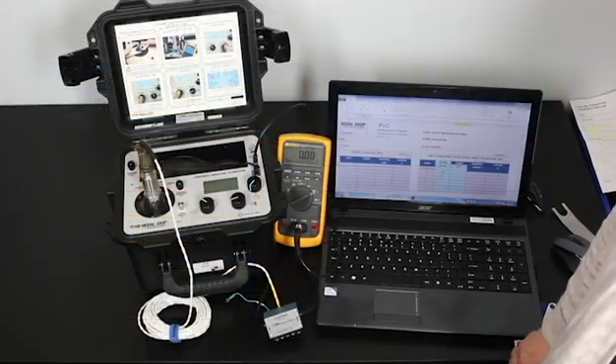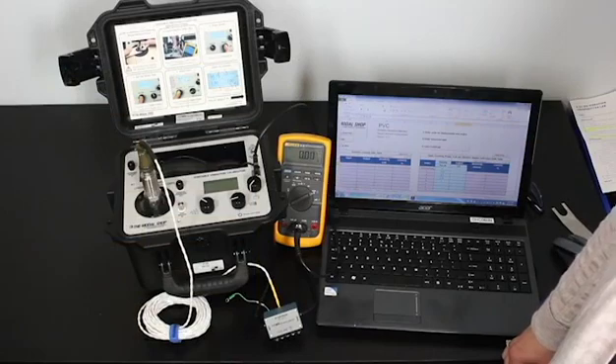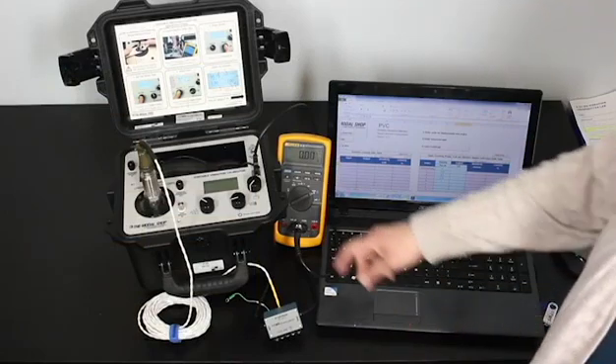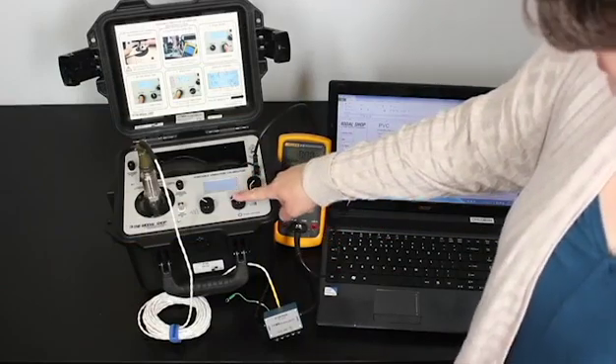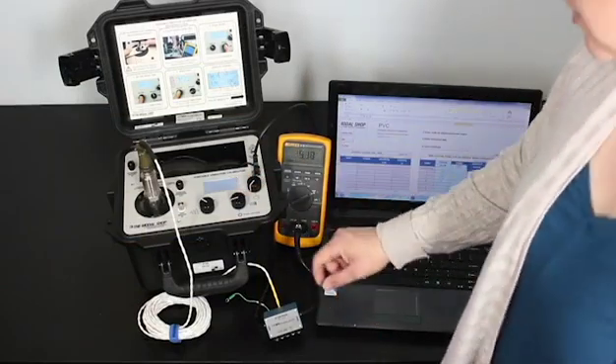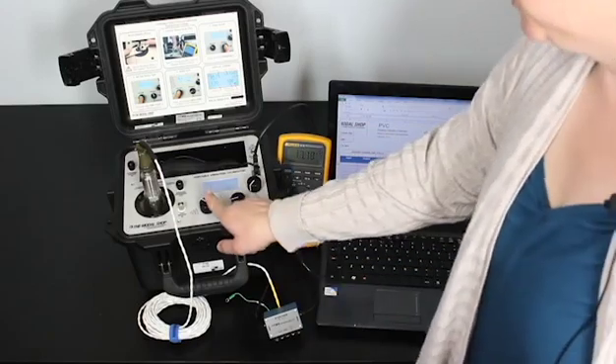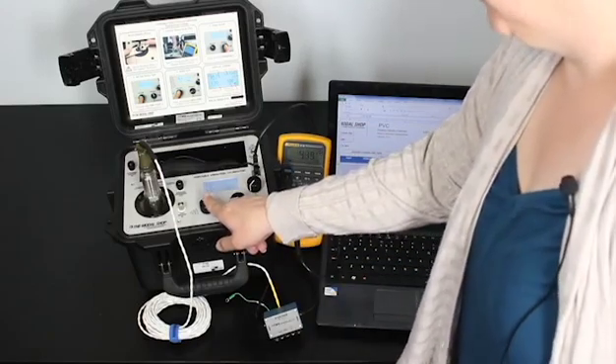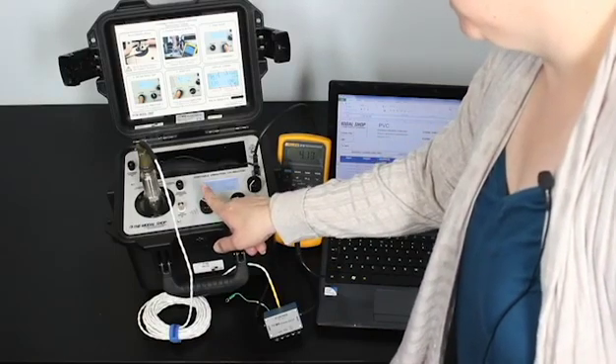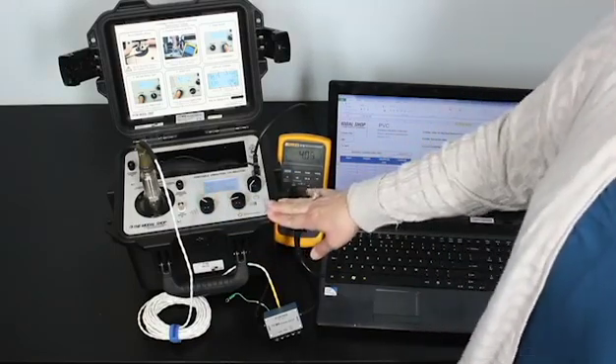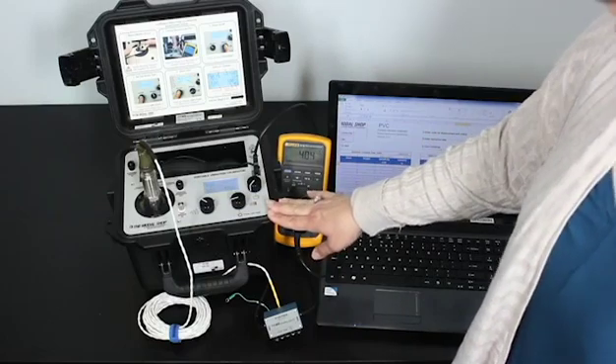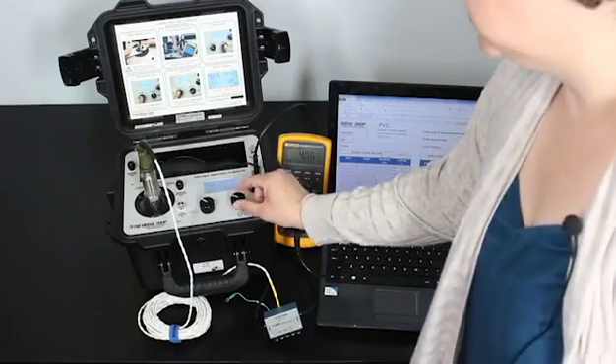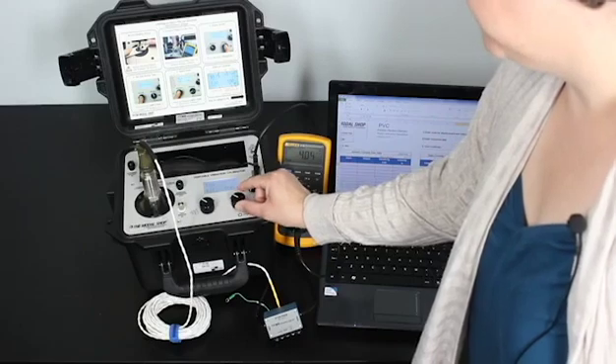Now that we're all set up, we're ready to begin the test itself. We are going to test at 5 different amplitude points evenly spaced through the sensor's range. So we'll turn on our portable vibration calibrator. And we want to make sure that our units for amplitude are set to inches per second peak. So we'll just press the amplitude button until we reach inches per second peak. There we are. We want our frequency to be set in cycles per minute, and it is. We want it to be at 1,800 cycles per minute. So I'll make that adjustment now.